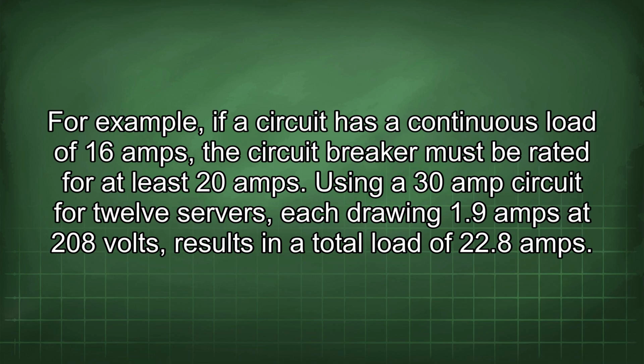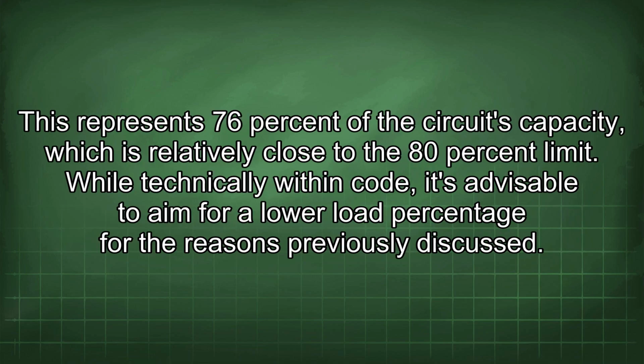least 20 amps. Using a 30 amp circuit for 12 servers, each drawing 1.9 amps at 208 volts, results in a total load of 22.8 amps. This represents 76% of the circuit's capacity, which is relatively close to the 80% limit. While technically within code, it's advisable to aim for a lower load percentage for the reasons previously discussed.